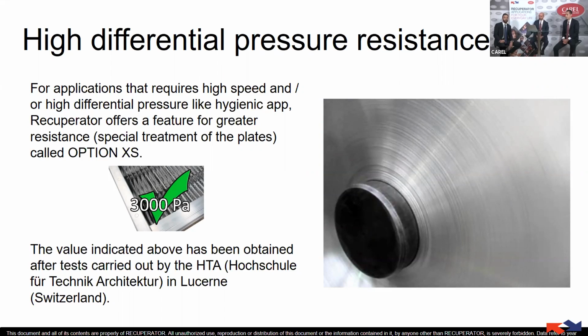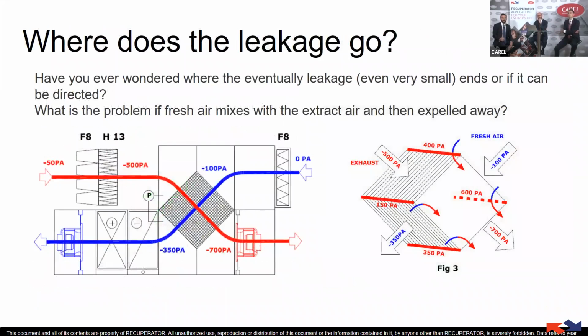Yes, exactly. That video wanted to show the deformation of the plates due to the differential pressure. It was accelerated, to explain that the differential pressure has a role in the functioning of the heat exchanger. And we were saying that in applications like hospital and hygienic applications, we can have high velocity and high differential pressure, which means the heat exchanger should support it. In some cases, with the right options, we can have a heat exchanger able to resist up to 3000 Pascal. But to go back to the poll before, the main characteristics should be fulfilled.